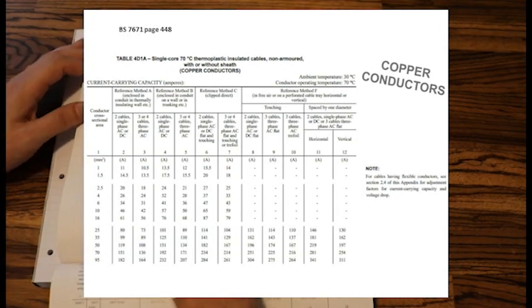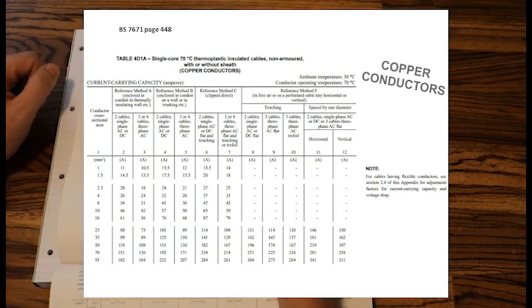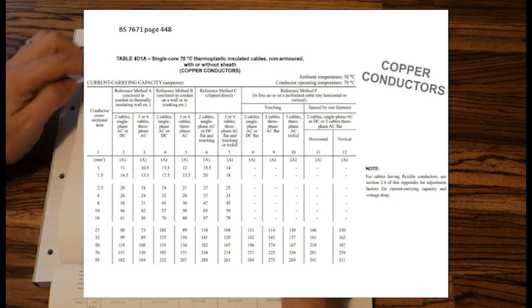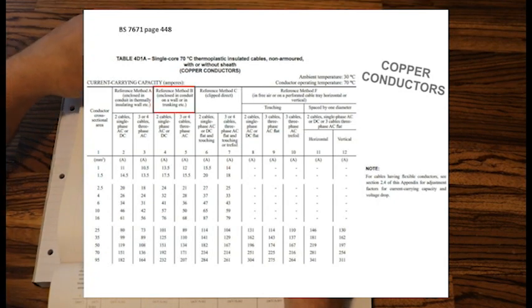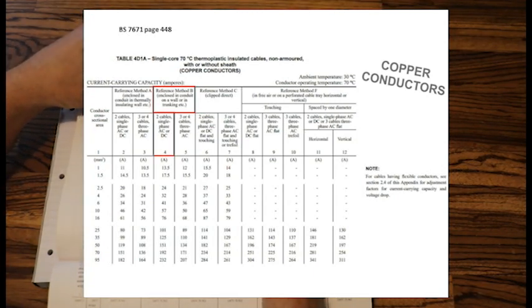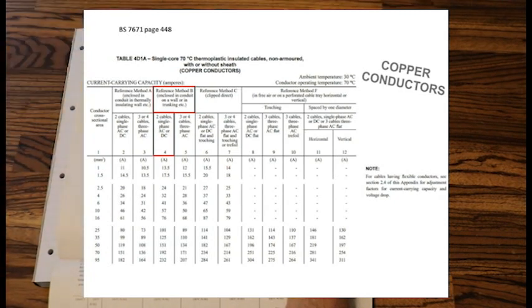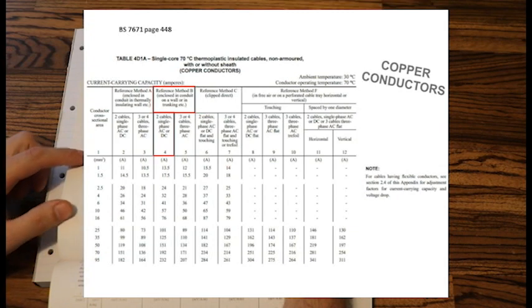Now we need to know the reference method. Our question was inside trunking it said, so we are reference method B, enclosed in conduit, on a wall, or in trunking. And we are single phase, so column 5 says 3 phase, column 4 says single phase, so we are column 4, and our IZ was 13.6, so we need 13.6 or above.